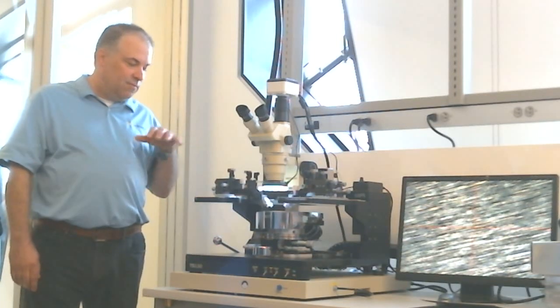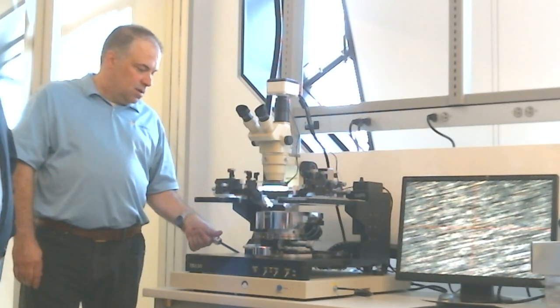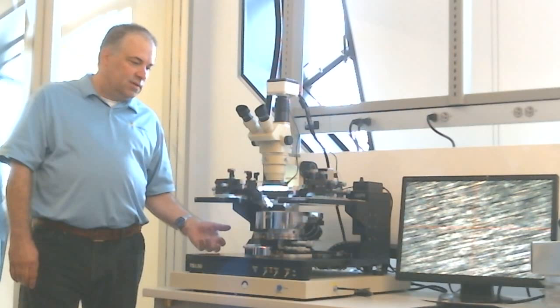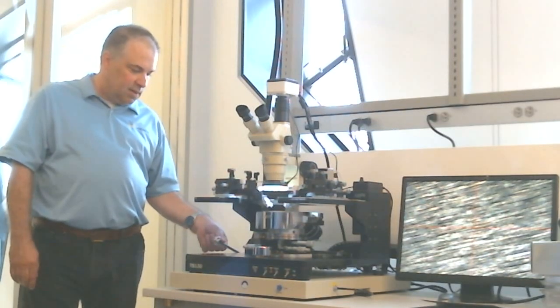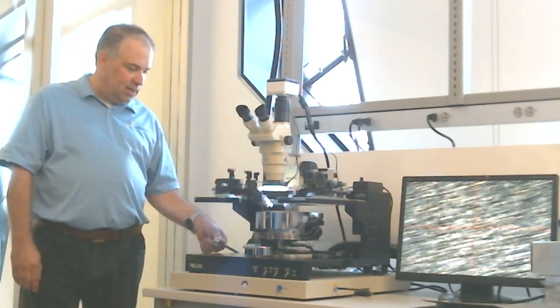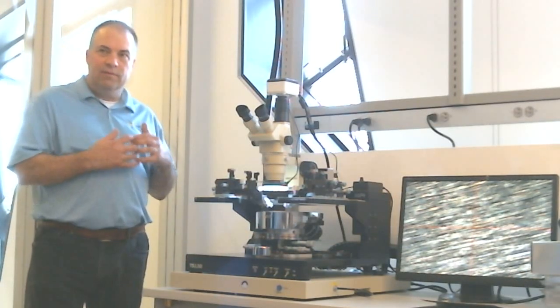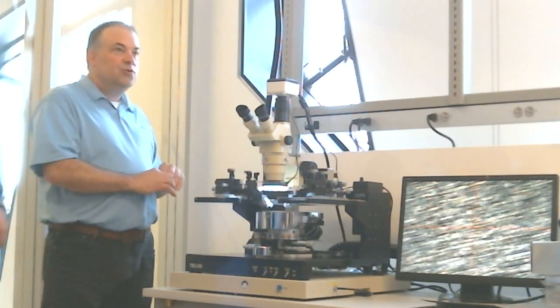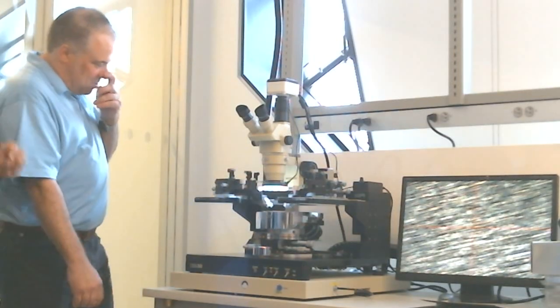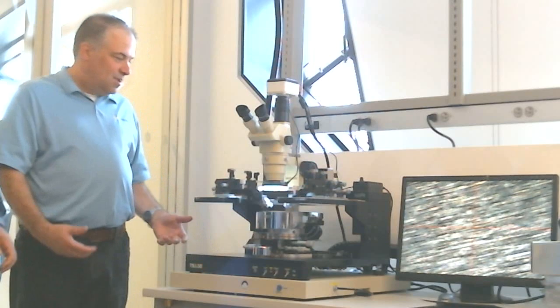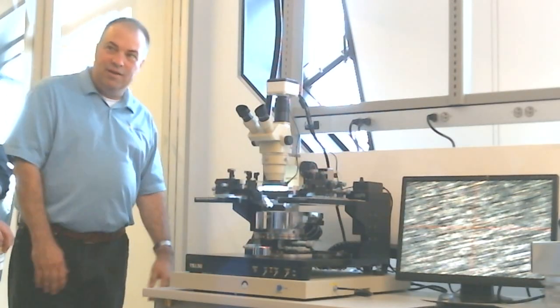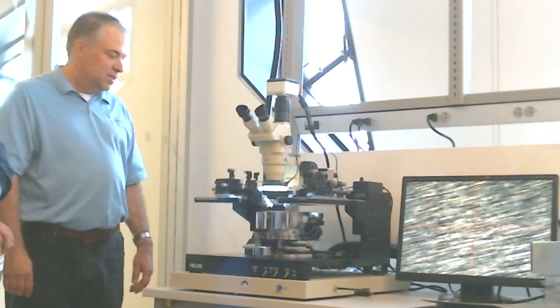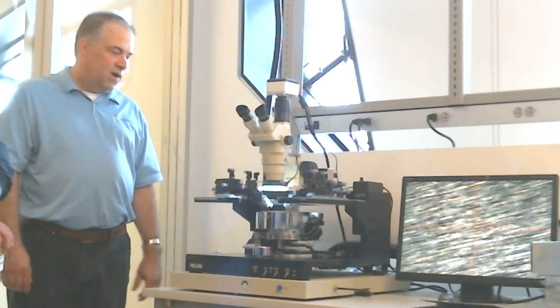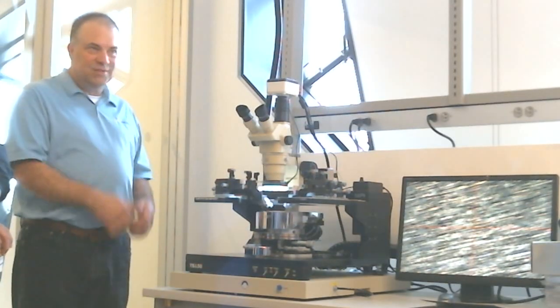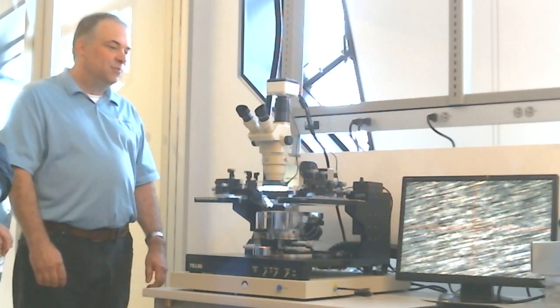And then if you want to go down to the final position, you just touch it and allow it to fall. You don't need to drive it down or bring it all the way down. There's a little detent here. Just overcome the detent and let it fall down. It's a very gentle, controlled dropping of the probes, and it's very, very repeatable within a micron. I demonstrated that to a couple of the gentlemen this morning. You can drop this 5, 6, 7 times, and it's going to be less than 1 micron every single time. So really, really good.